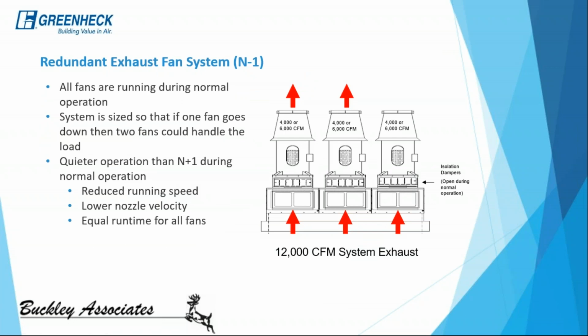On the other hand, there is a second type of system, so that would be N-1. So here we have the exact same 12,000 CFM exhaust system. However, all 3 of the fans are going to be running at the exact same time at some sort of partial load. So let's say they were all running at 4,000, 4,000, and 4,000. If one of these fans goes down or is shut down for maintenance, the other 2 fans are going to be designed to be able to ramp up and then carry the full load and split 6,000 CFM apiece.